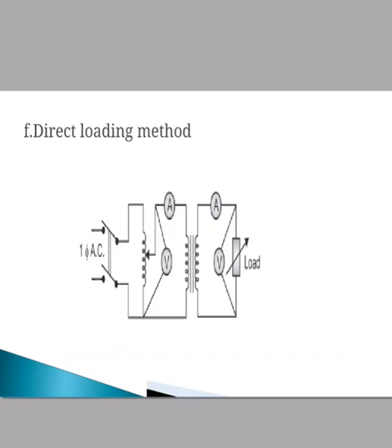But as the size of the transformer increases, the loading arrangement may not be available due to non-availability of high power supply, problem of heat dissipation, etc. This method is not suitable for large size transformers. The more important point is the loss of energy due to such a test. Hence, direct loading methods are not preferred in comparison to the indirect method of temperature rise.